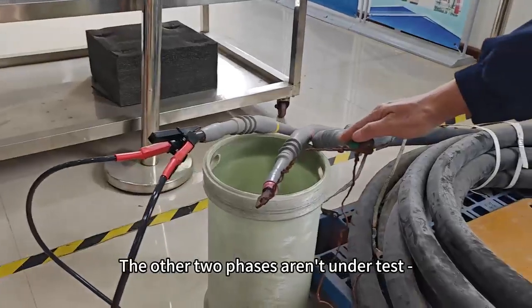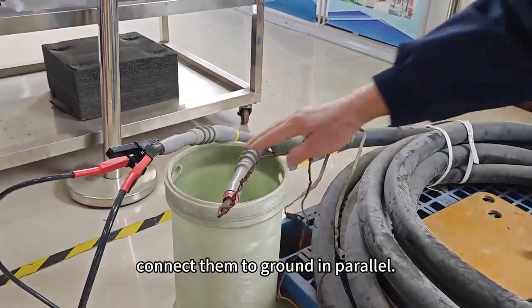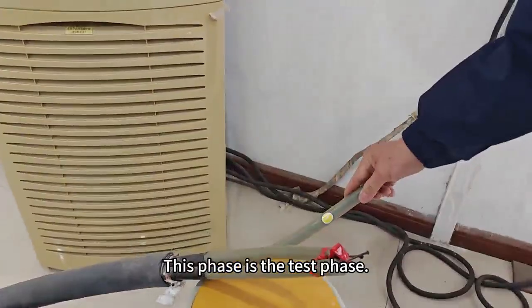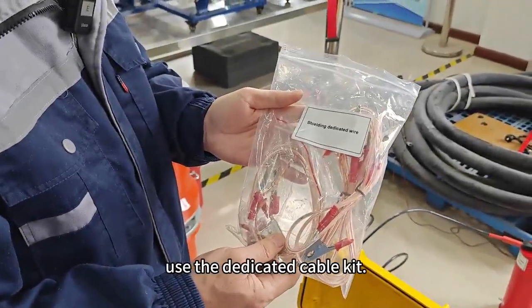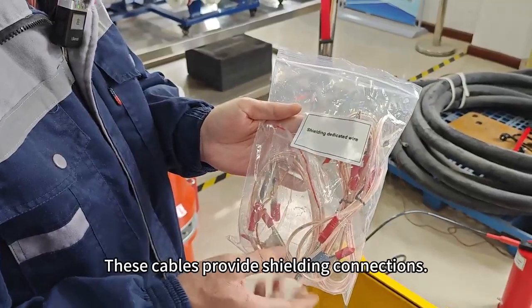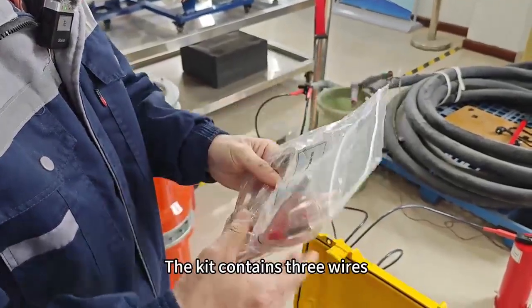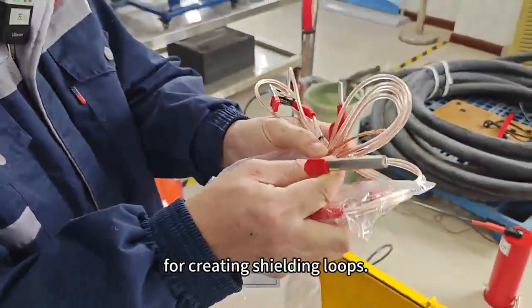The other two phases aren't on the test. Connect them to ground in parallel, at the cable's far end. This phase is the test phase. The other two aren't measured. For dielectric loss testing, use the dedicated cable kit. These cables provide shielding connections. The kit contains 3 wires, with bare copper ends, for creating shielding loops.